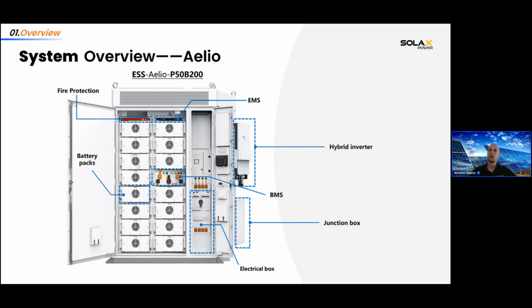The overview of the AELIO is kind of similar to the rest, because you can see if you open the front doors, you can see the battery packs. Each battery pack is around 14 kilowatt hour, and in the middle you have the BMS. You have fire protection on the top and the energy management system too. On the side you can see the hybrid inverter where you can connect the DCs, the AC cables, the communications. You have the junction box and an electrical box inside the cabinet. And when you order this kind of ESS and when you get it delivered to your site, it will be already pre-assembled, so you don't have to connect any kind of cables inside the battery. You just have to install the PV connections to the inverter and do the electrical wiring to the junction boxes. So it's really easy to install and saves you a lot of time and money.